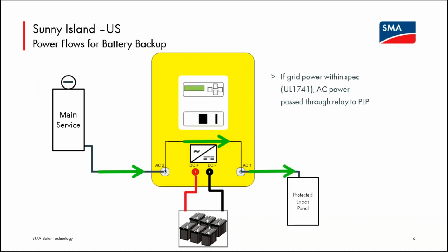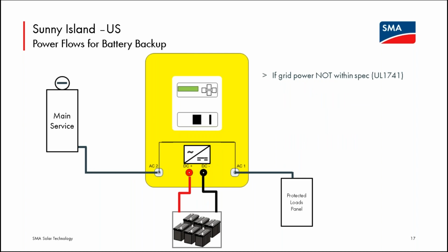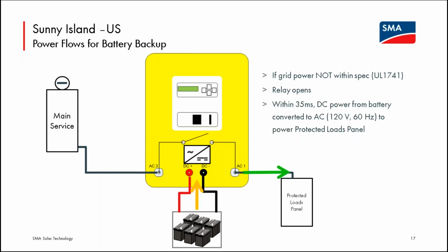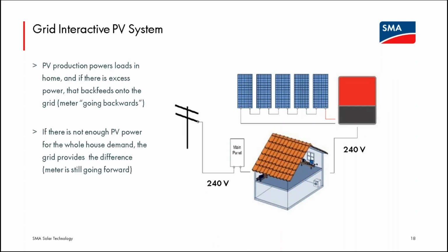So just a quick overview. In grid-tied battery backup, the Sunny Island is a UL 1741 listed device. So just like a PV inverter, as long as that utility grid is within spec, it will operate and interact with that grid. And in this case, it can pass power across its isolation relay to the protected loads panel. If that goes out of spec for frequency or voltage, very, very quickly the Sunny Island will open its transfer relay, isolate everything downstream, that is the protected loads panel, from the faulted grid, and within a maximum of 35 milliseconds, take power from its battery bank and create the 120 volt, 60 hertz grid to power that protected loads panel. So most users and most loads will never even notice this transfer time. Very, very quickly, it will step in and become the utility grid.